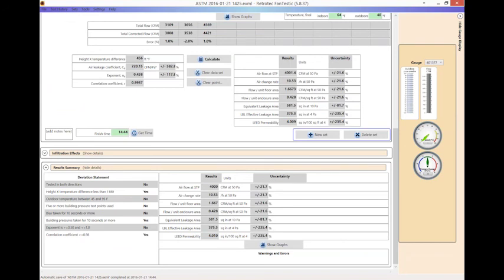All right. So there's a temperature difference and a height ratio from outside. It says you've met that. My outdoor temperature should be between 45 and 95, and it is not. Did I not do enough baselines, or did I? I did do my readings at 10 seconds. So whether or not you completely adhere to all of the deviation statements is based upon your test requirements, or the standard that you're going to follow with your client, or how you perform this test.